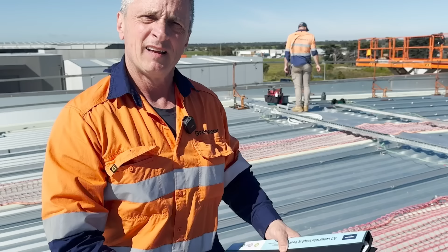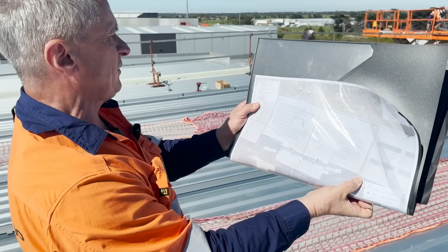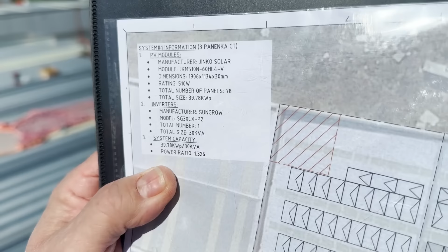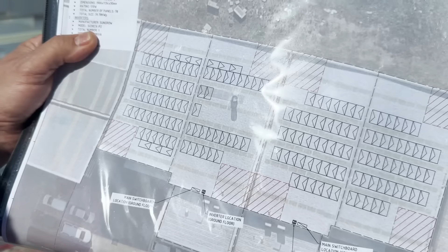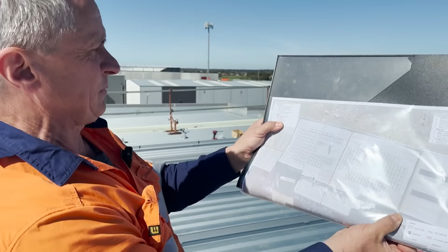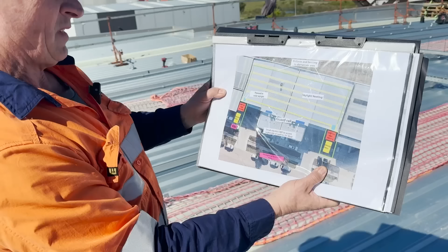Okay, so I'm holding one of the most important documents you have on a commercial solar system, and that's the recipe book. What I mean by that is effectively we're talking about the certification, for example with the guardrail, other important documents, and very importantly, the actual drawings of the string configurations of the panels. So effectively, this is the panel configuration here. You're talking about Jinko solar panels, 510 watts each, 78 panels, total of 39.78 kilowatt peak, and that's for roof one. Obviously, we're using a Sungrow here, a 30 kilowatt Sungrow - well, actually 30 kVA, let's be precise about this.